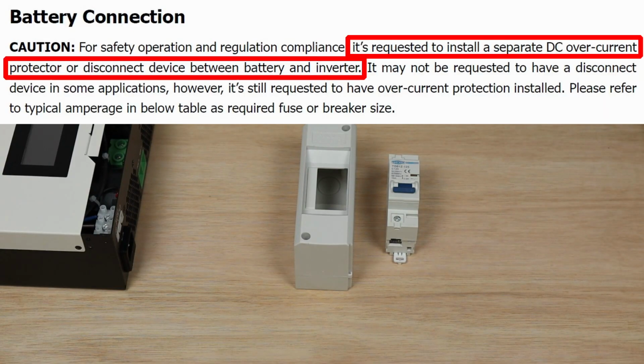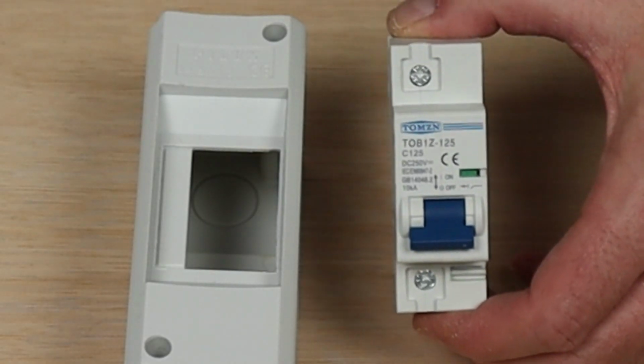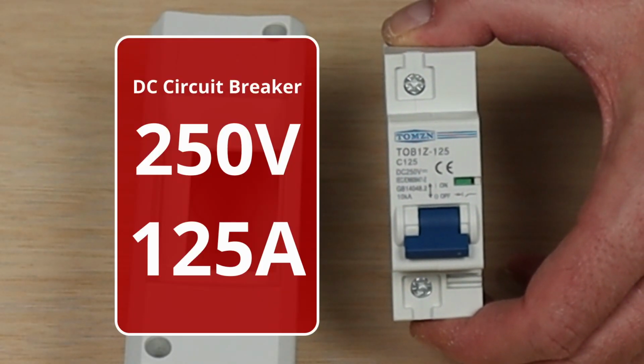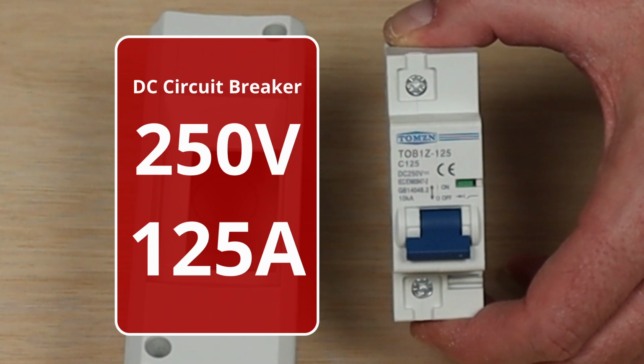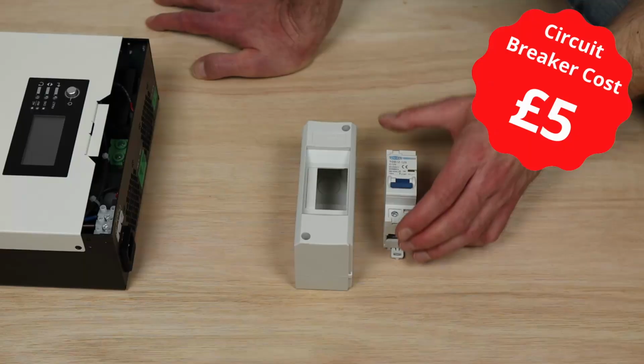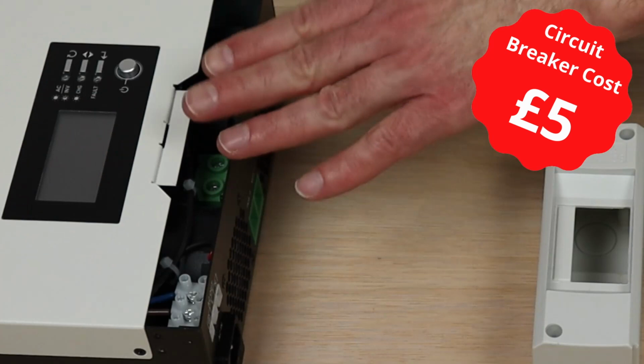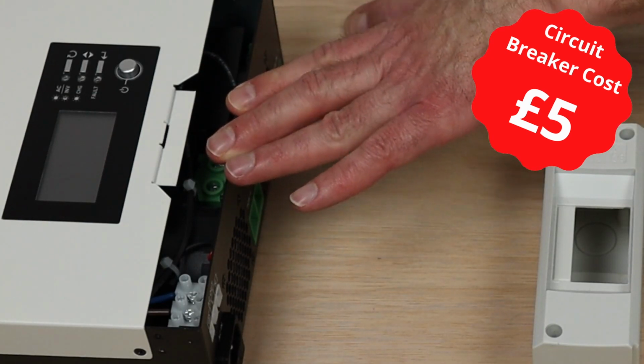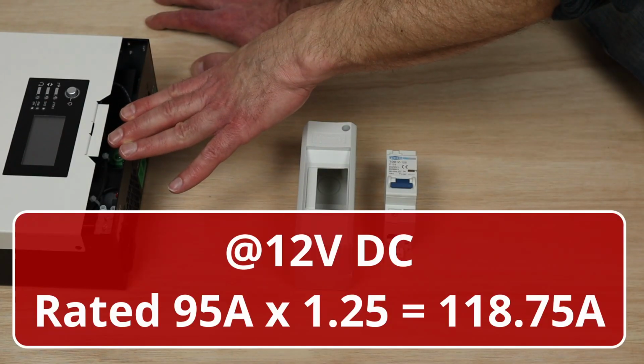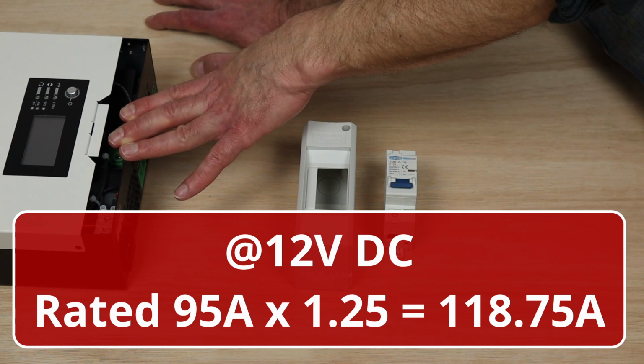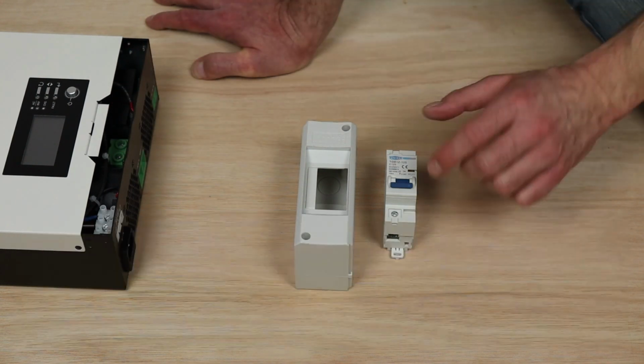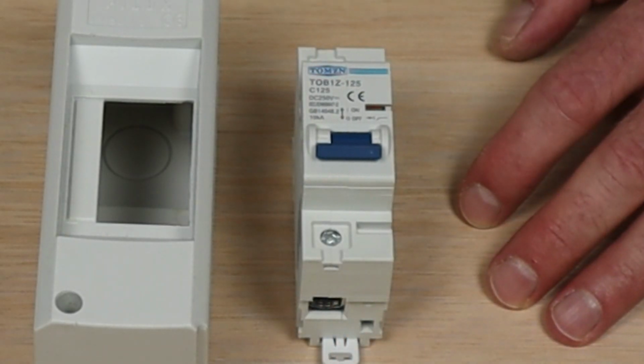The manual recommends having some kind of separate DC overcurrent protector or disconnect device between the battery and the inverter. In my case, I'm going to use this DC circuit breaker - a 250 volt version, good for 125 amps. I picked this particular one because it can handle almost 100 amps at 12 volts. Normally you apply a rule of thumb of 1.25 to get your fuse or circuit breaker ratings, which is why I've chosen the 125 amp version.